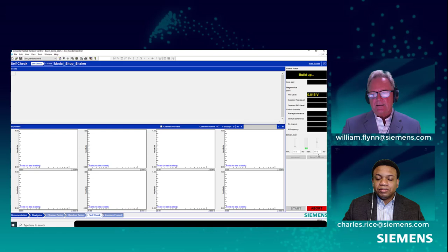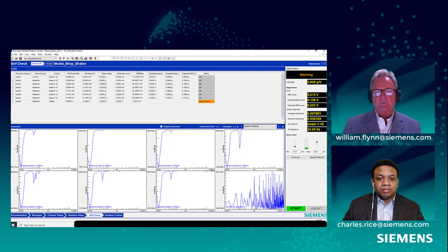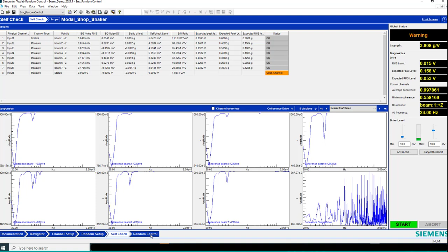Notice I've got a minimum here of 10 millivolts and a maximum of 20. So I think I had steps of 4. So you see the first RMS level is 15 millivolts. And it made it to the first level, and my signal to noise ratio was over the threshold. So it continues on. It met the minimum requirement, and it met the signal to noise ratio. I have all okay channels. I get a global status of warning because of this open channel, and I'm not measuring anything on that. I'm actually measuring the status signal coming out of the DAC, and that's why it's an open channel.